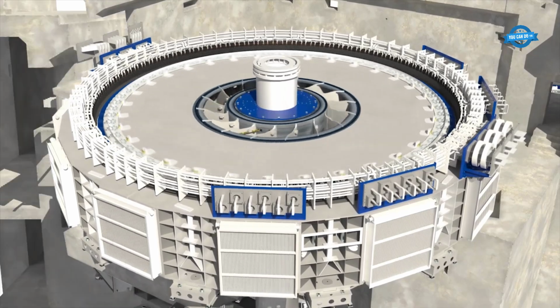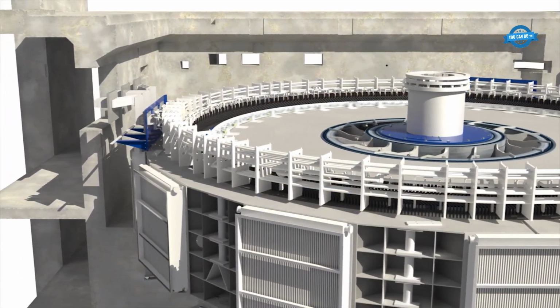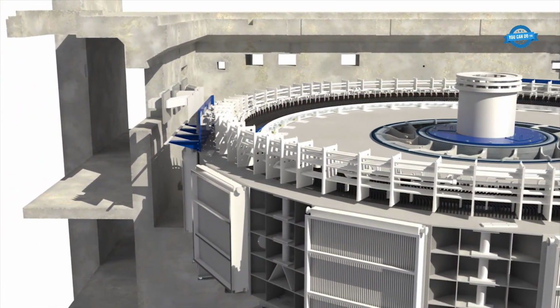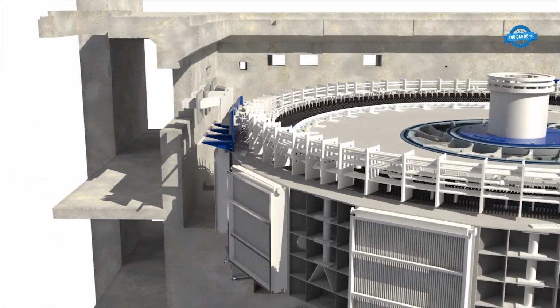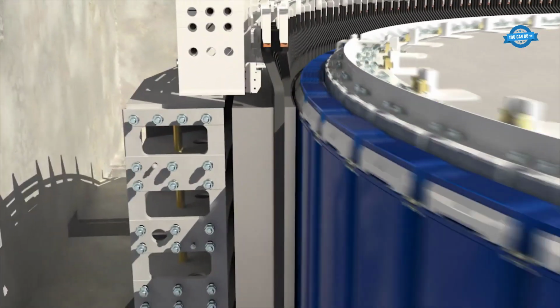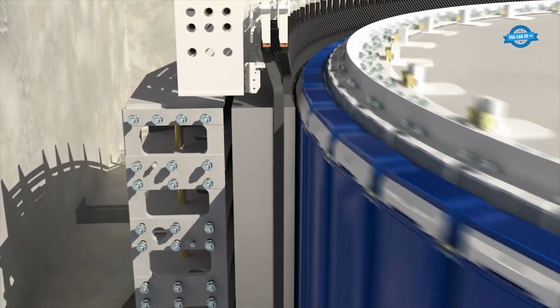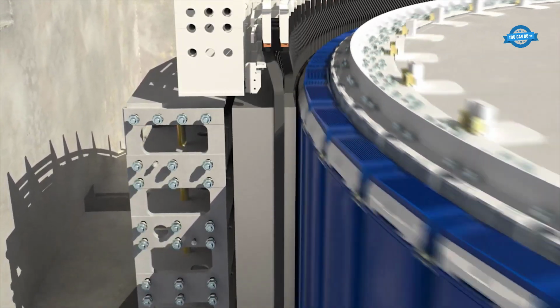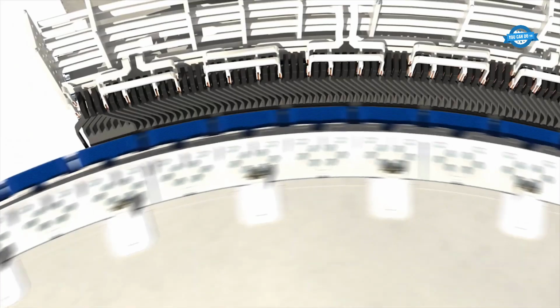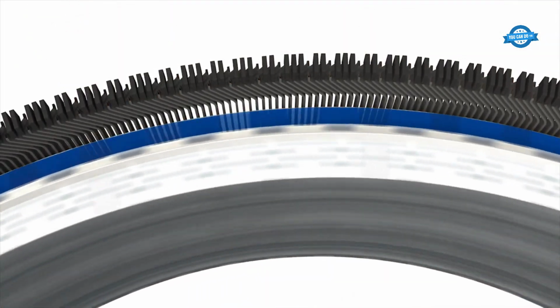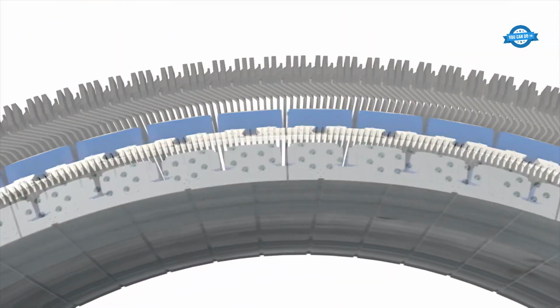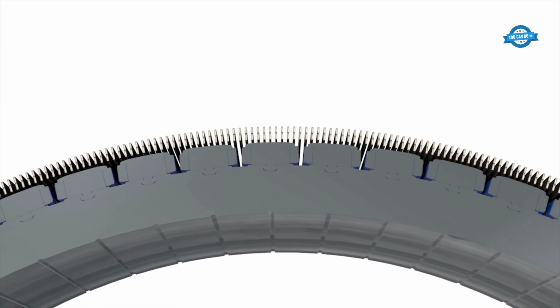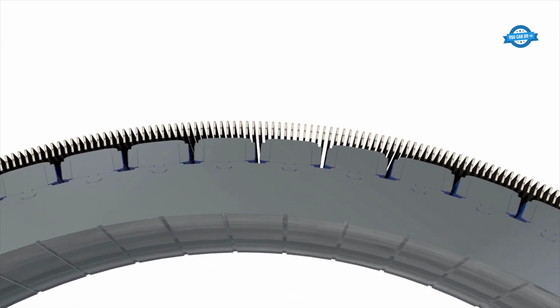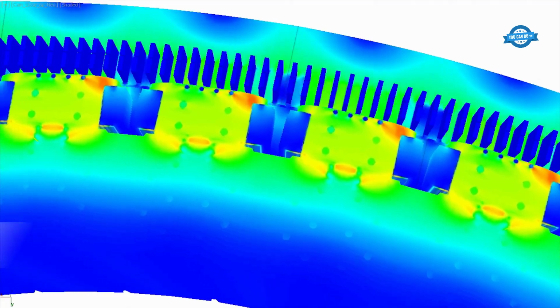The intricate design of these generators takes into account several crucial factors. Operational temperatures must align with material limits, ensuring longevity and reliability. The moment of inertia is carefully calculated within the stator bore dimensions to enhance grid stability, extend the time until the power unit reaches runaway speed, reduce water hammer pressure, and guarantee effective turbine regulation at shutdown.